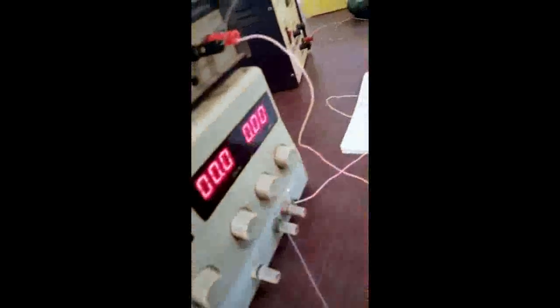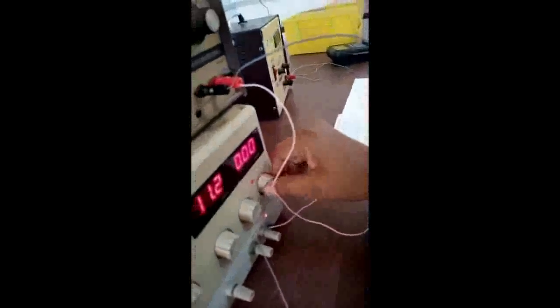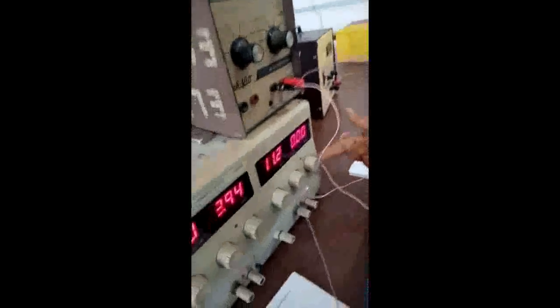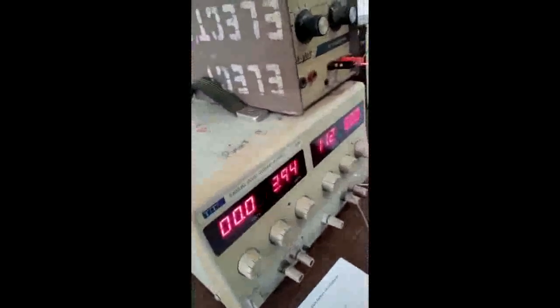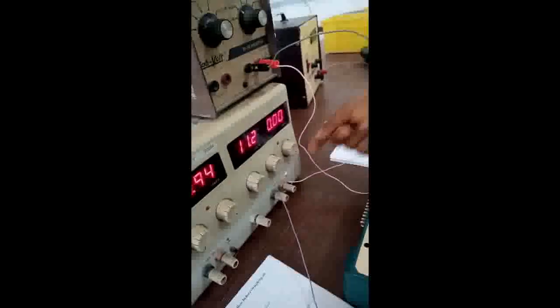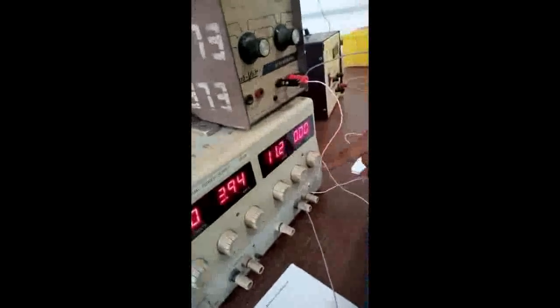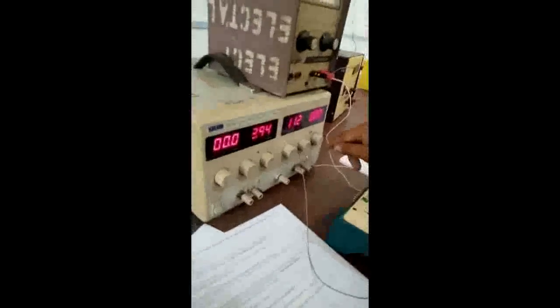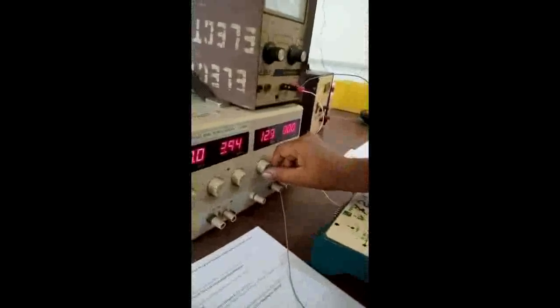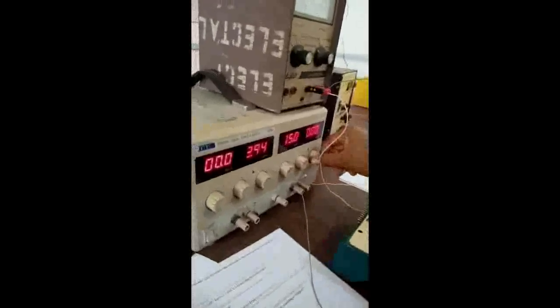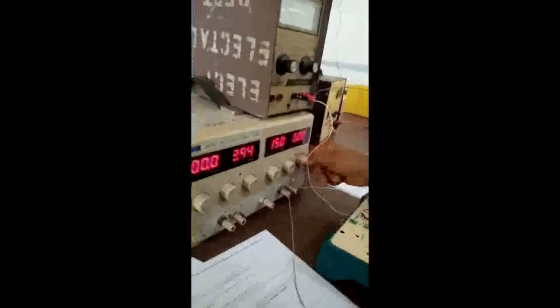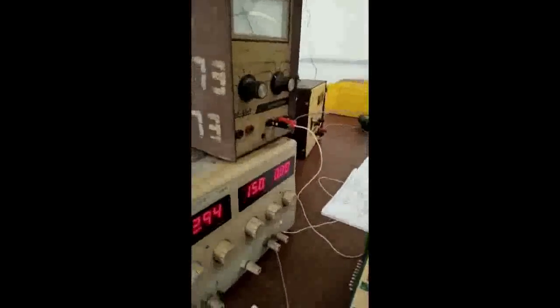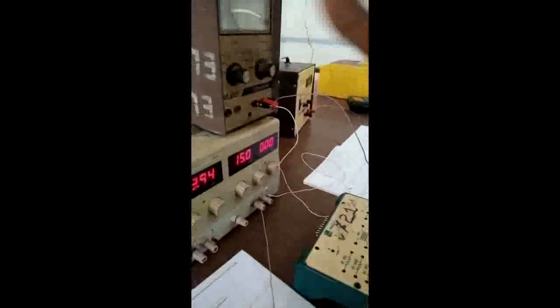This current control knob, for current you have to set it fully clockwise. Don't forget, while we were using it the other time to get a reading for the voltmeter, this current control knob was set in the reverse direction, that is fully counterclockwise. Now because we want to take a current reading, we are setting this one fully clockwise. Now this, you have to set it to the given voltage value, which is 15 volts. And this current control knob, that is current limit, must always be fully clockwise, either you are using it for a voltage reading or you want to get a current reading. It must always be fully clockwise for you to have a reading on your voltmeter or your ammeter.